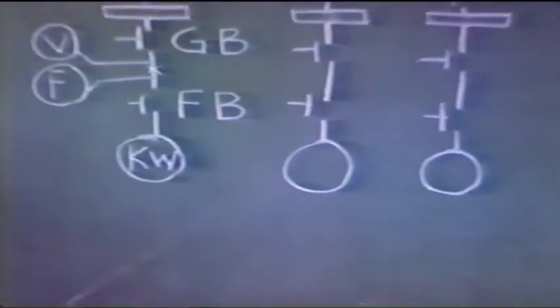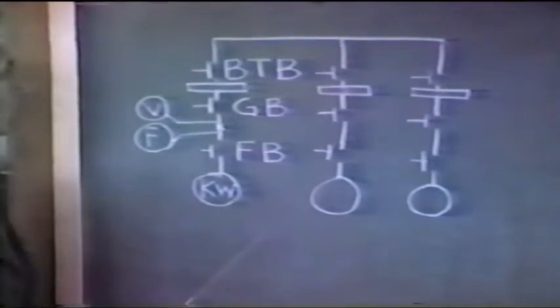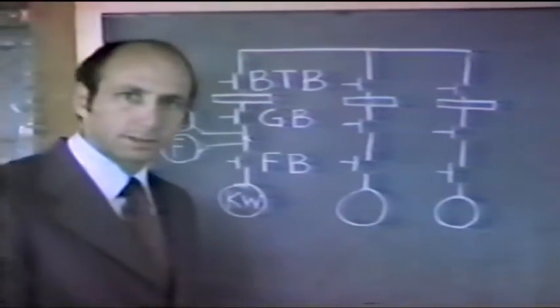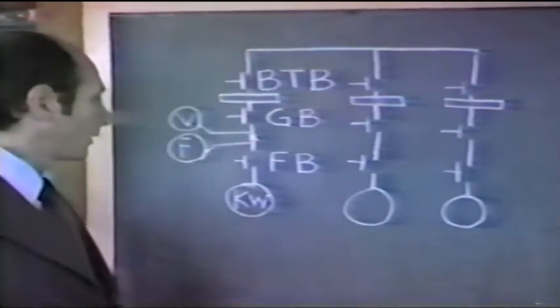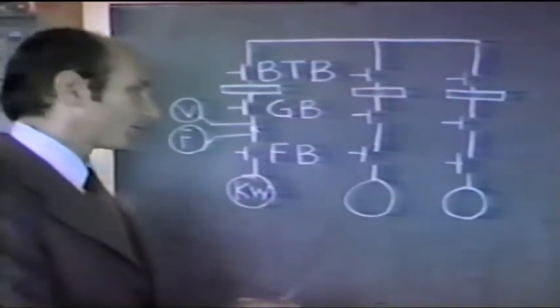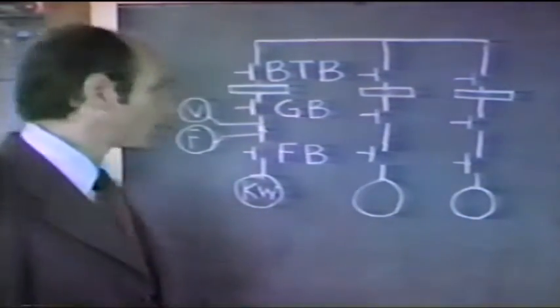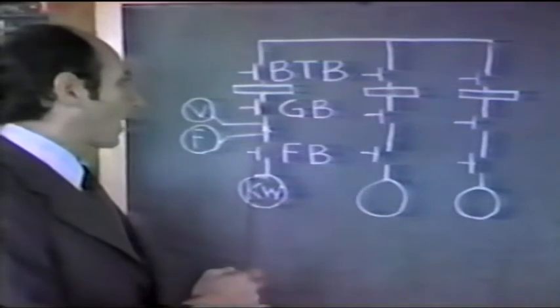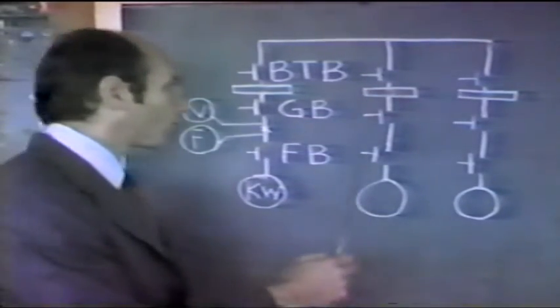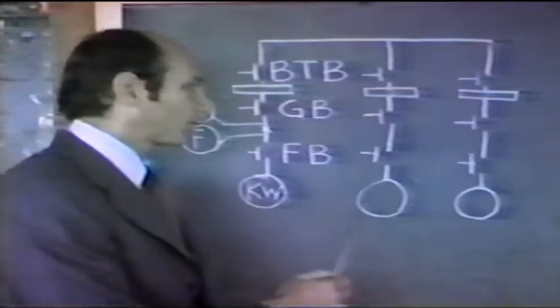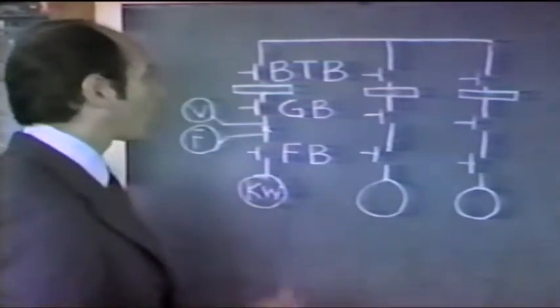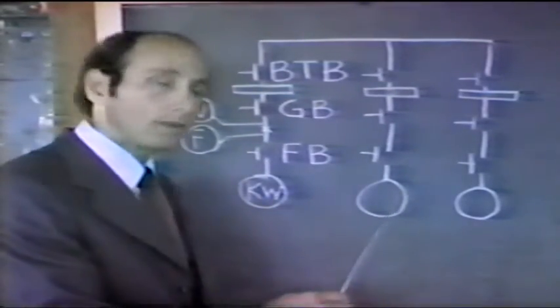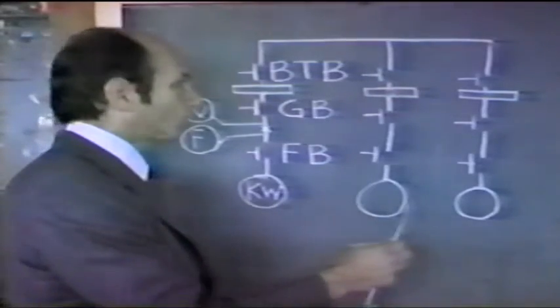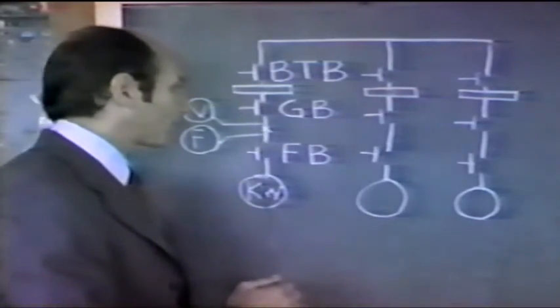So let's look at what we've got so far in terms of the electrical system. We've got 3 generators, each going through a field breaker, which serves as the on-off switch for the generator. And then the output to the respective load bus is controlled by the generator breaker. And then we can tie all 3 load buses together through the bus tie breakers. Once again, manual paralleling, automatic paralleling.